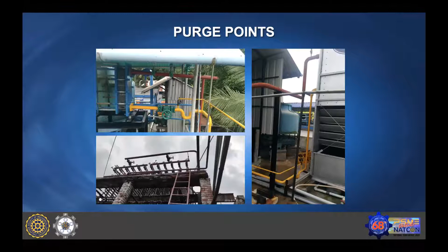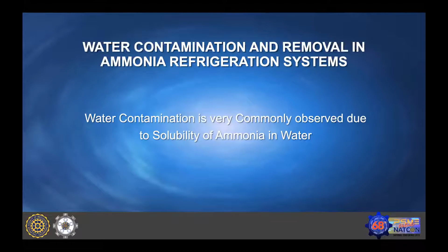So this is all about air purging, or the effects of air. So let's go to the effects of water, or what happens with the effects of water in an ammonia system. Water contamination is very commonly observed due to the solubility of ammonia in water. What it means is that ammonia has a very high affinity to water, and if water and ammonia come in together, they mix and form an aqueous ammonia solution.